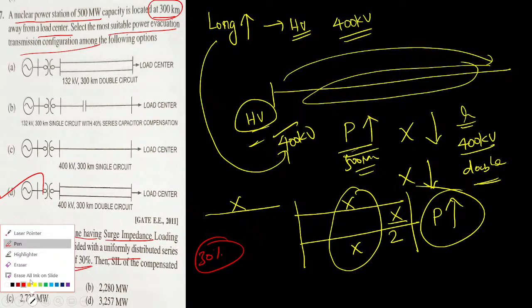Tell me. One minute, let me remove these things. Yes. So surge impedance loading of the transmission line will be equal to voltage, that is surge voltage, V square divided by characteristic impedance for per phase. For a 3-phase transmission line, you will have to multiply it by 3. So 3 times V square, that is per phase voltage, divided by characteristic impedance. Voltage will be per phase in both cases. Anyway, in transmission line, it doesn't matter. They have not talked about single phase or 3-phase at all. So I'm taking the general formula for surge impedance loading.